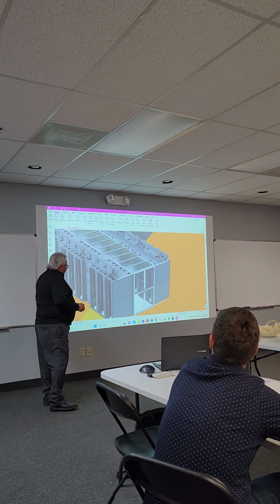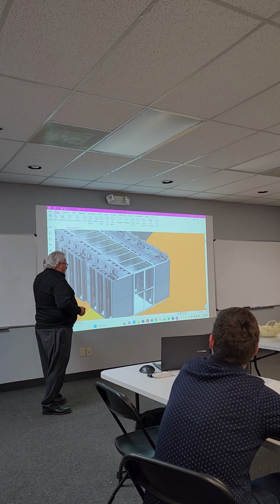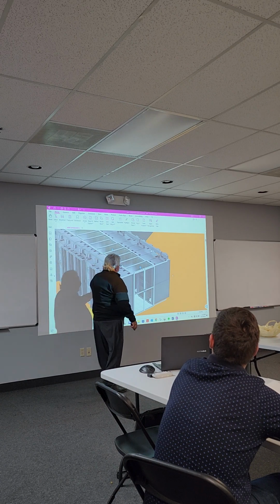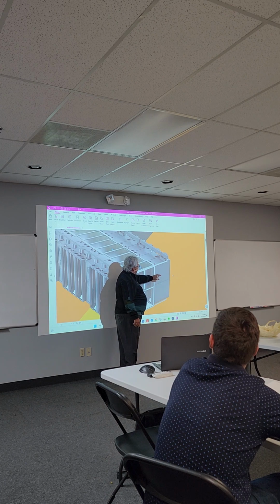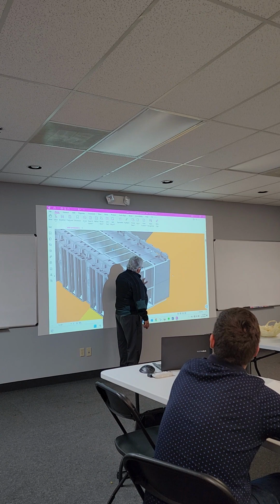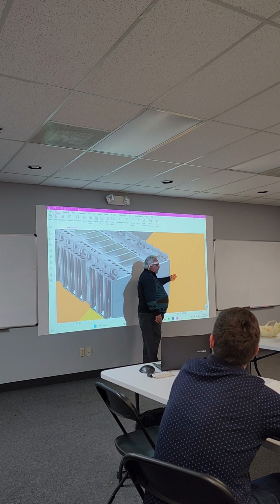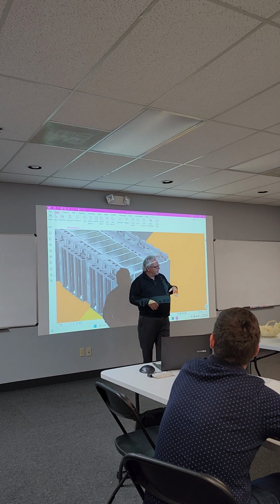But I'd say the one biggest thing is this right here. If you did this, let's say on that drawing I showed you before, if you were to put a door, picture this: here's that row of racks I was talking about, cold aisle here. If you enclose this, the cold air has nowhere else to go but through the rack, it cools the server down, the heat comes out the backside and goes back to the unit. So now the room is like a return air plenum.